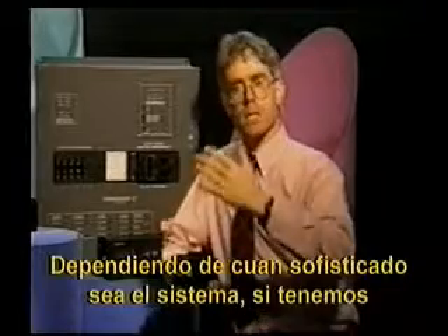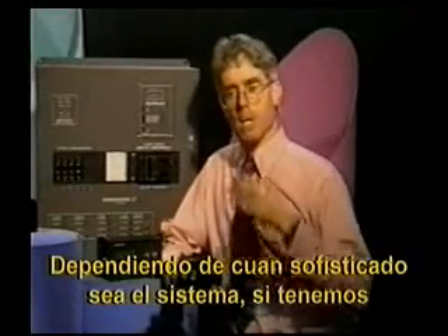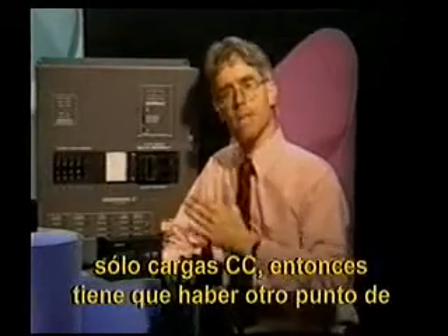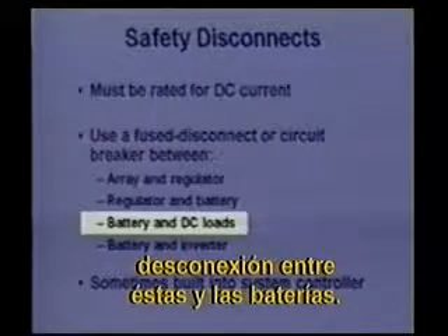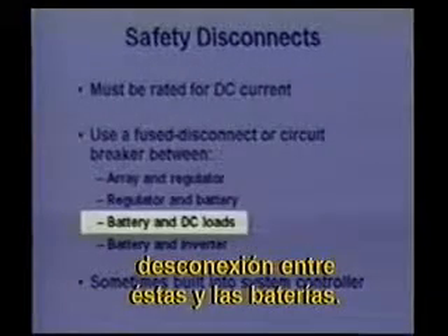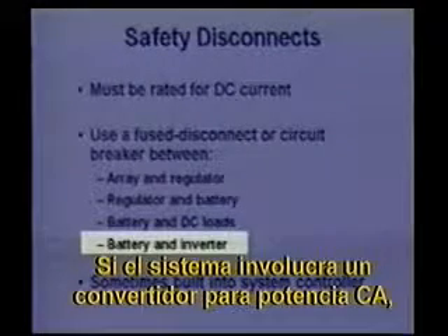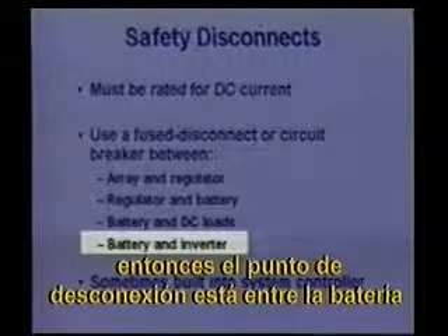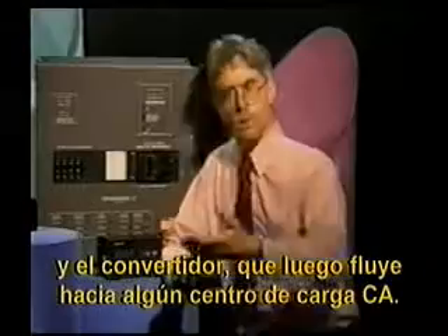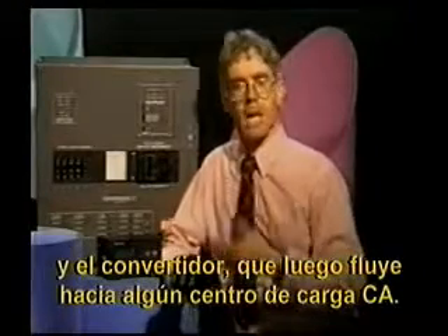Then, depending on our system sophistication, if we have just DC loads, we'll want to have another disconnect point between our battery and our DC loads. And if we have an inverter involved for AC power, we want to disconnect between the battery and the inverter, which is then flowing on to some sort of AC load center.